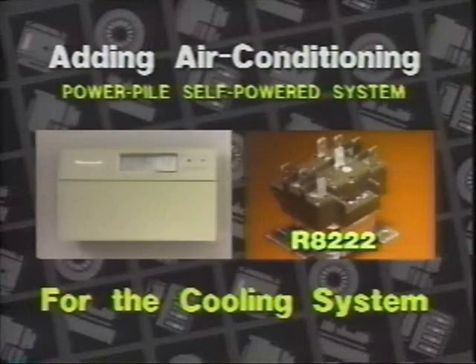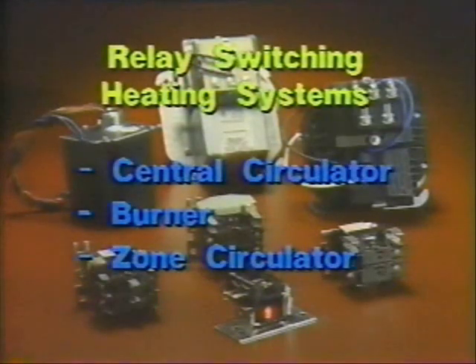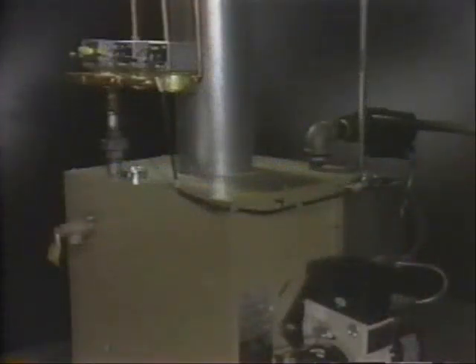While we've concentrated on air conditioning systems up to now, relays also play important roles in heating systems. Key functions include central circulator switching, burner switching, and zone circulator switching. Honeywell has 3 relays that can do a variety of jobs in heating systems. All have built-in transformers to provide low-voltage power for control circuits.